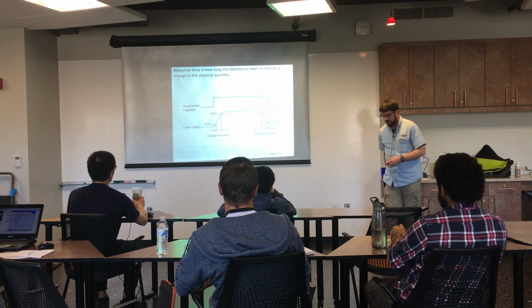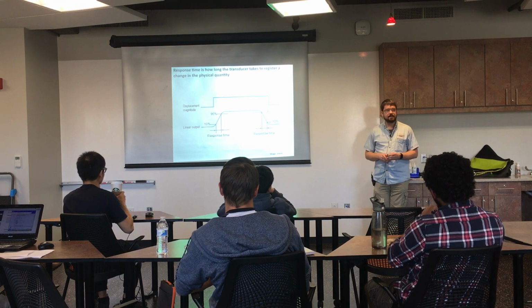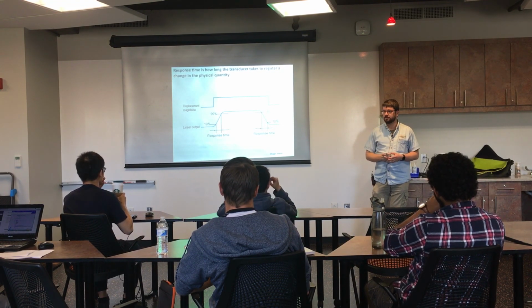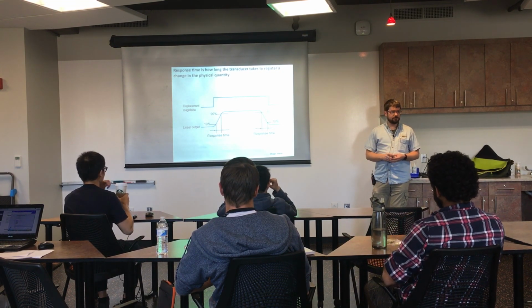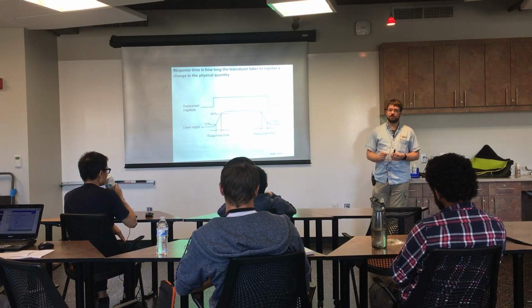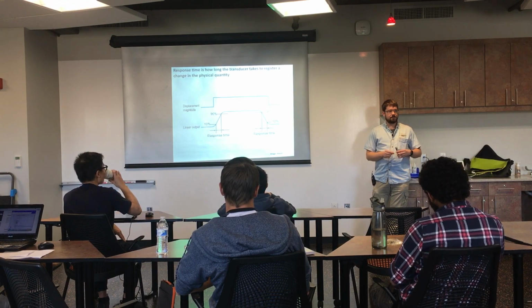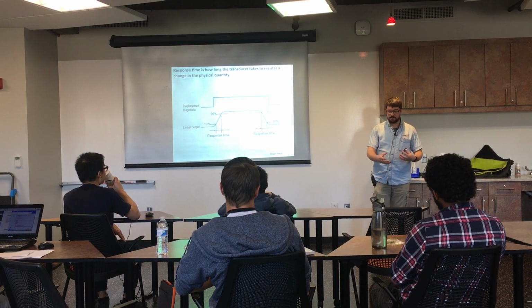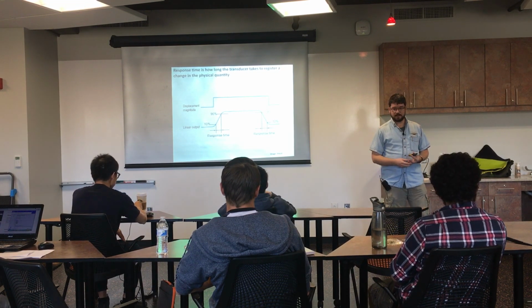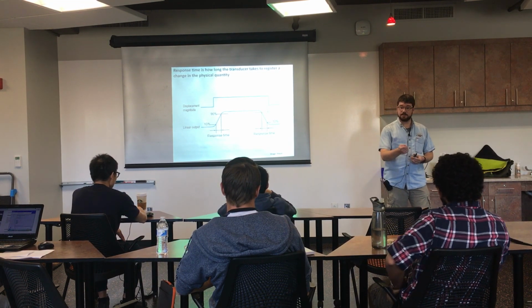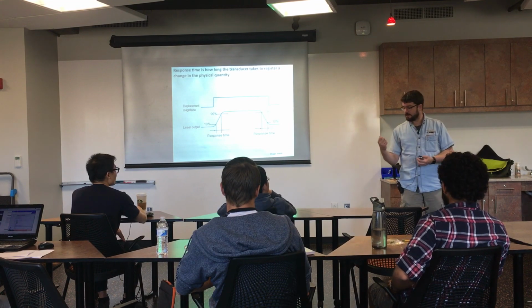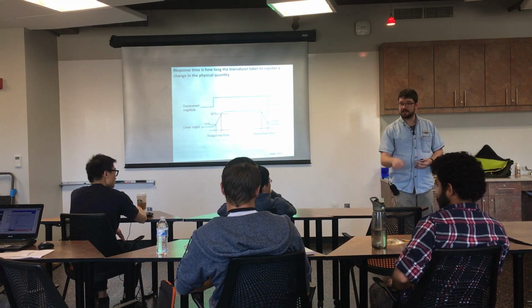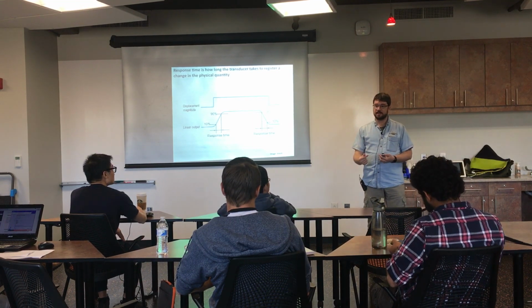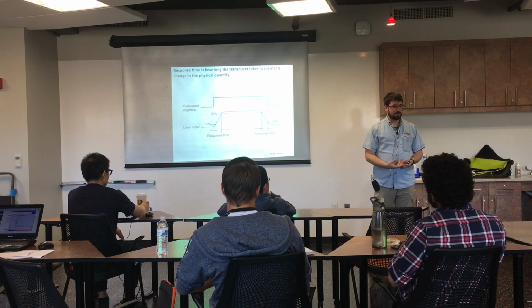Another one, and one that gets left out of consideration a lot, I find, is the response time of the transducer. There is no such thing as a transducer that instantly responds to a change in the system. So you're going to have something. If it's a mechanical sensor, maybe you've got some inertial effects. If it's a temperature sensor, and I stick it on a hot plate, it's not going to instantly jump to the temperature of the hot plate. It's got some thermal mass that we have to overcome.